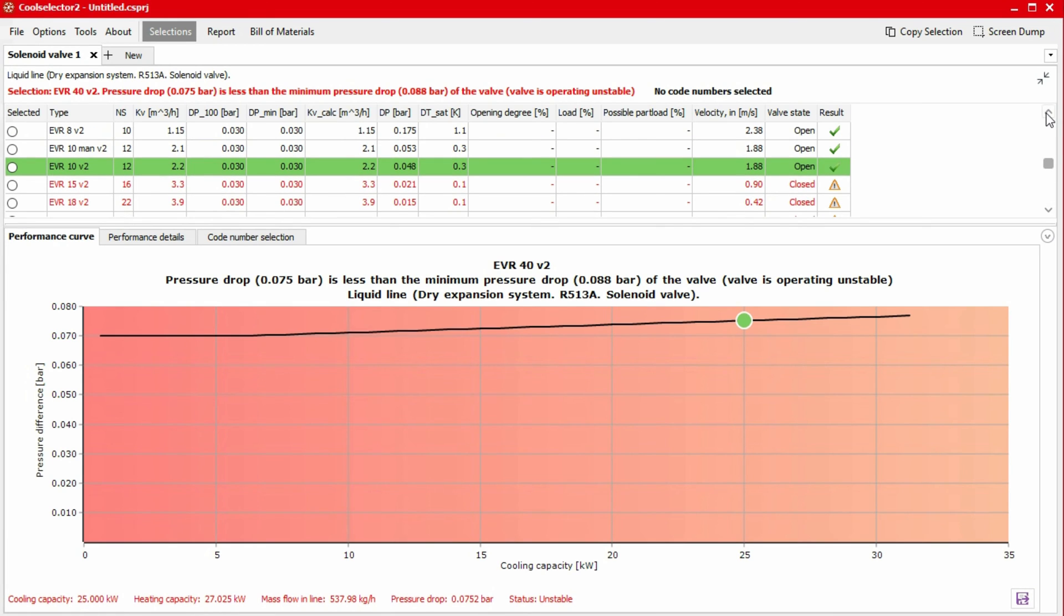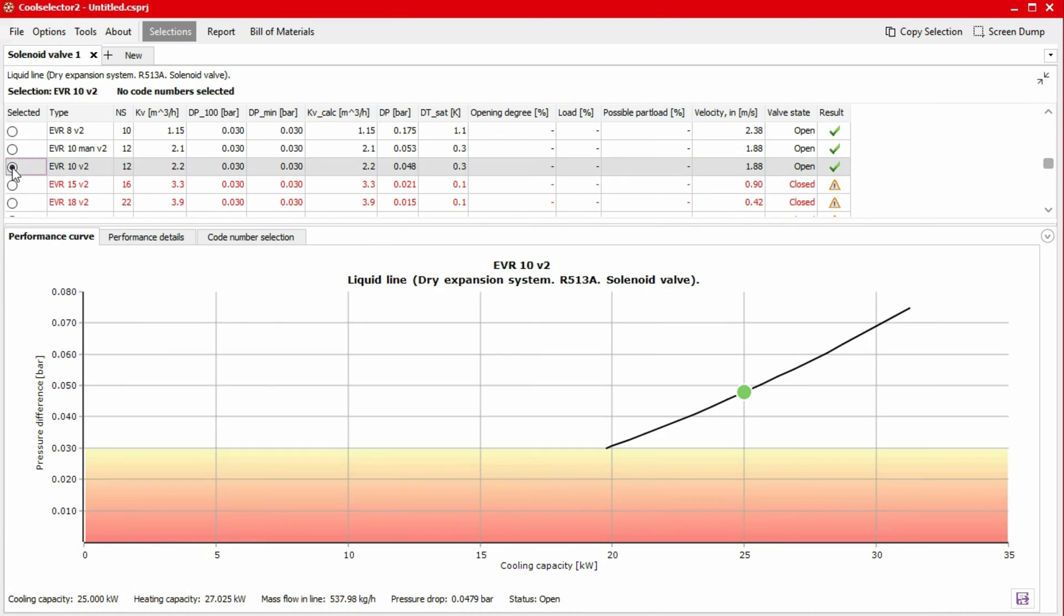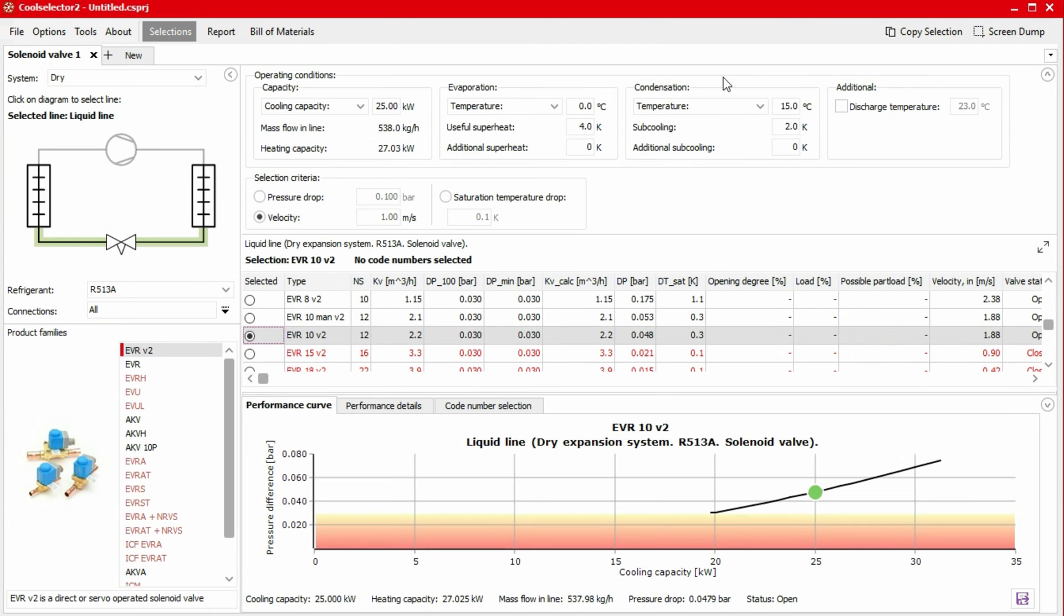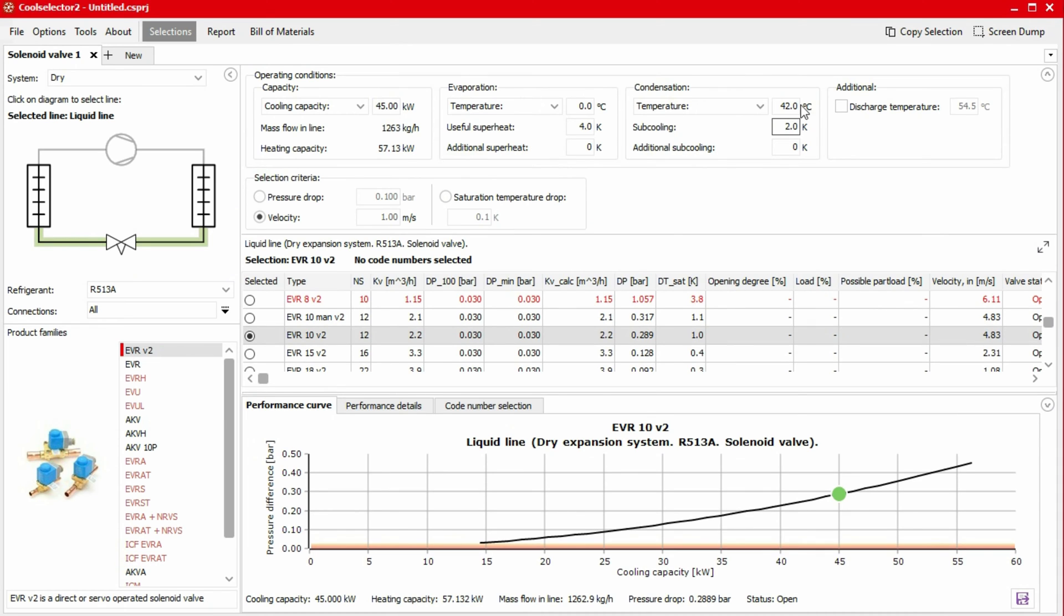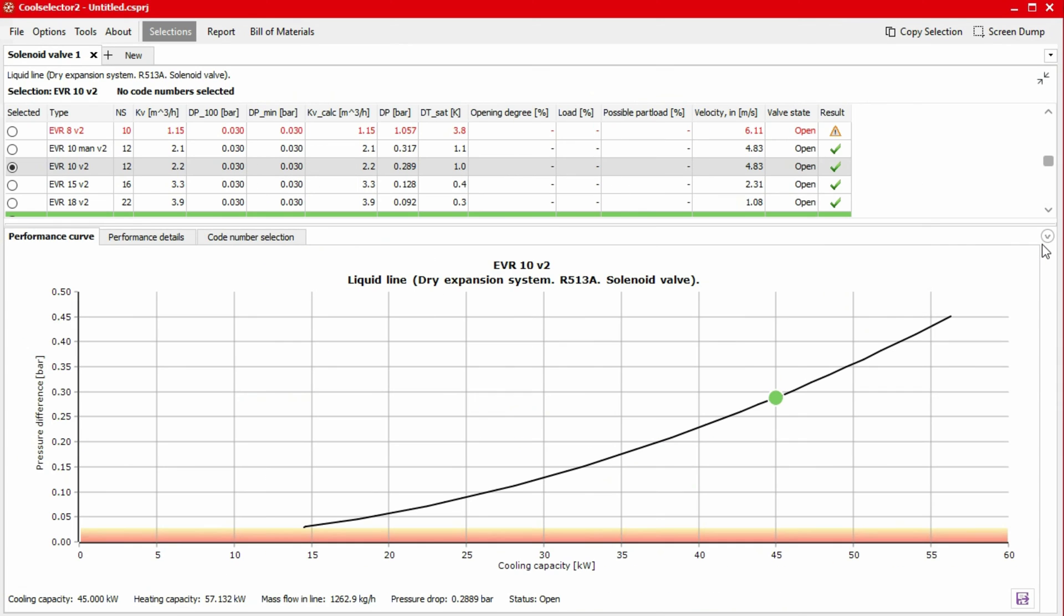Now we see that the EVR10V2 is suggested, and in the graph, we see that it can handle this cooling load at winter conditions. If we then keep this product selected and change our cooling capacity back to 45 kilowatts and the condensation temperature to 42 degrees, we also see this valve is capable of handling our full load of 45 kilowatts, so we will select this valve.